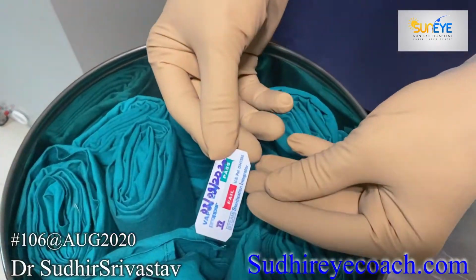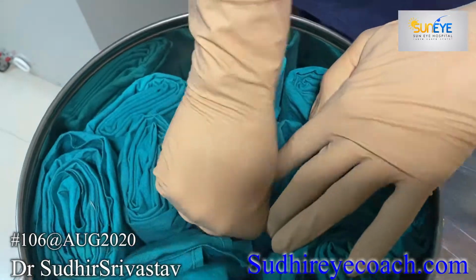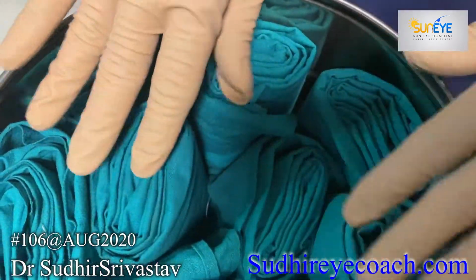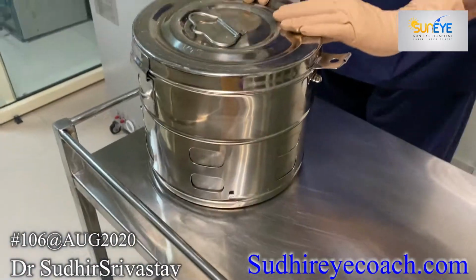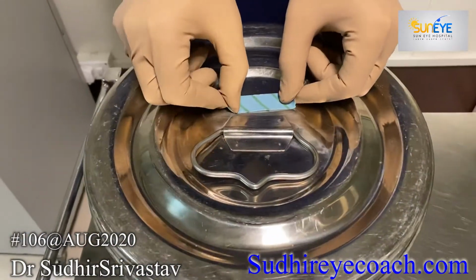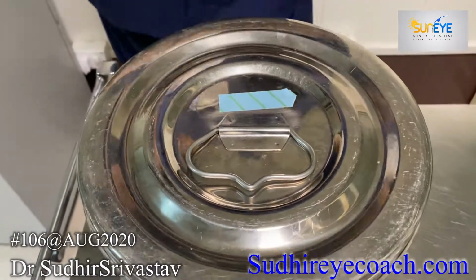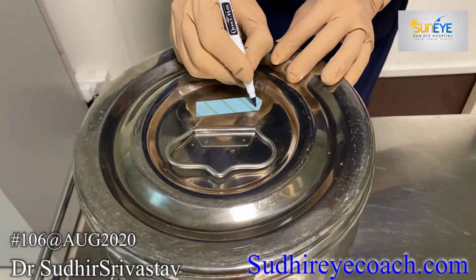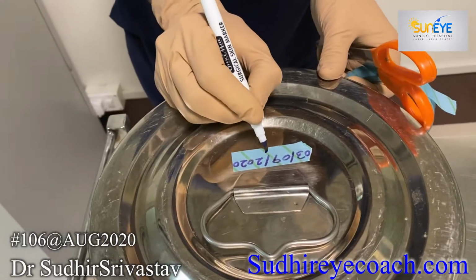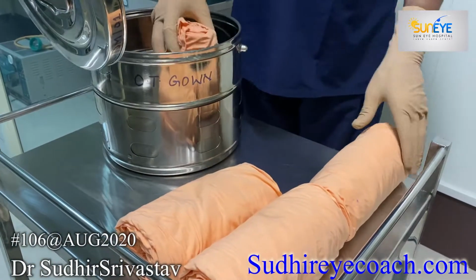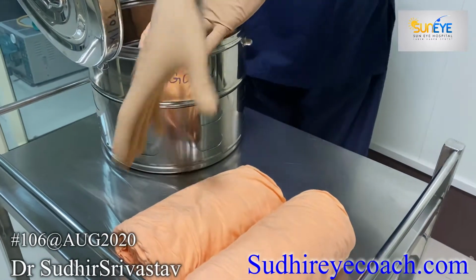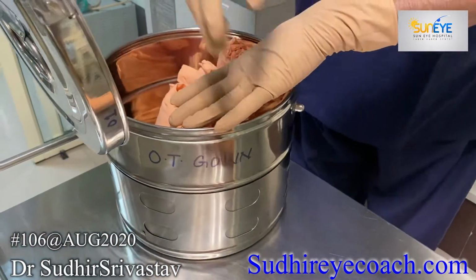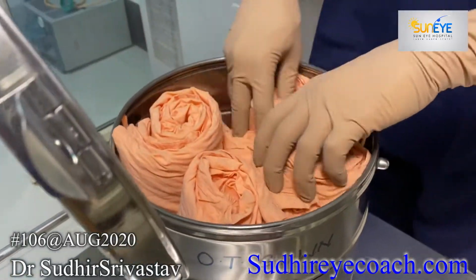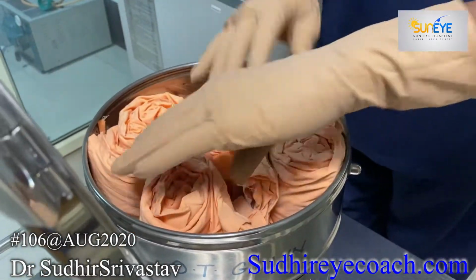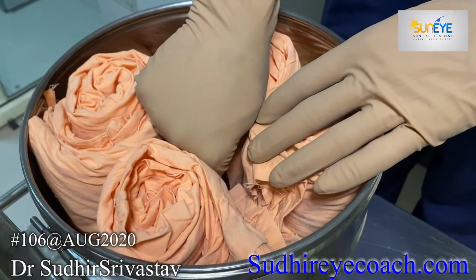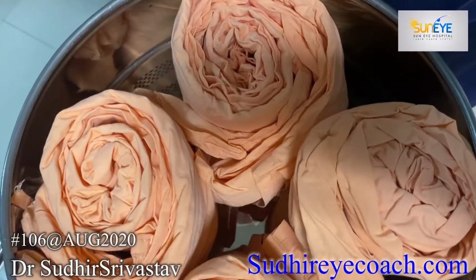planned properly. To check the quality of sterilization, a type 5 integrating indicator is placed inside the drum, which is supposed to be the most resistant area for steam penetration. Now stick the type 1 strip indicator on the top of the surgical drum and label it for the records. Every sterilization process must be documented. Every surgical drum must be prepared in the same way and it should be labeled. Type 5 integrators read all critical variables in the sterilization process, whereas a type 1 strip indicator assesses one or more critical variables.